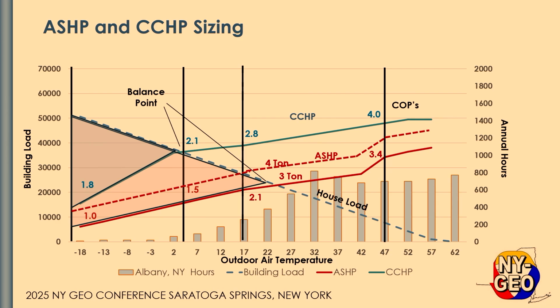And so you run a COP down here, even though the COP is relatively high, you're not getting a lot of capacity out of it because of the air temperature. So this triangle here would still need to be made up by some sort of auxiliary heat system, either electric or gas. And even though it's smaller and you can see that the COP is an improvement, anytime you've got any hours down here, you're either going to shut the heat pump off, shut the auxiliary heat off, which is going to make the occupant uncomfortable for that period of time, or you've got to use gas or something else if you want to keep it off the grid.